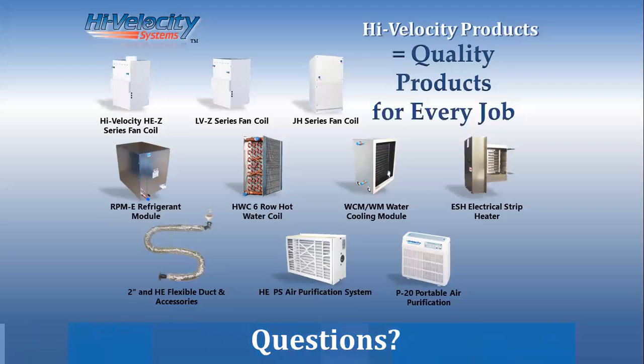I can tell you in states such as California, where they've adopted really intense regulations on HERS rating requirements for mechanical in structures, as well as blower door testing of the homes and duct leakage tests, our contractors always pass with flying colors on our high velocity duct system. I can't think of a contractor to date that has failed the duct leakage tests that are required in states like California and Massachusetts that have very high energy conscious requirements for their installations.